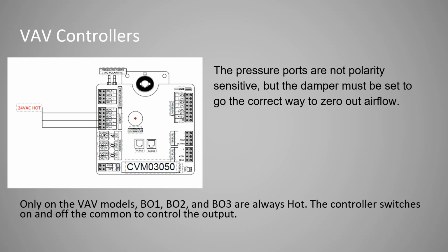If you're doing a VAV box, you've got to be careful what's being shared across the terminals in that box, okay? So the contactors, if it already has a common going to it, this common right here, it's not going to work when you fire BO1 common, okay? Then you just have two commons. That doesn't work. That doesn't make a circuit.